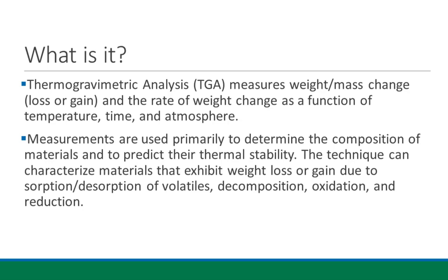Hello and welcome to the theory and background section regarding TGA. The first thing to cover is what is TGA? TGA stands for thermogravimetric analysis. Thermo meaning heat, gravimetric regarding the measurement of the mass, and analyzing the results. This technique measures the mass change, either positive or negative, and the rate at which it occurs as a function of temperature, time, and atmosphere — such as nitrogen, which is an inert atmosphere, or air, which would be an oxidizing atmosphere.